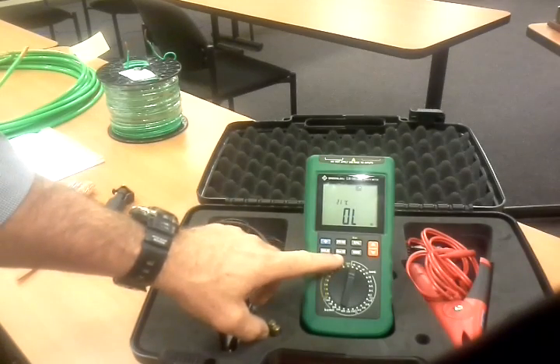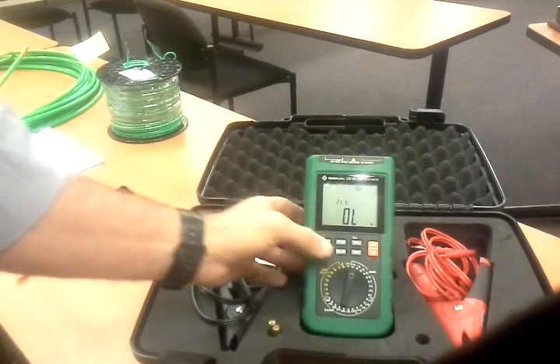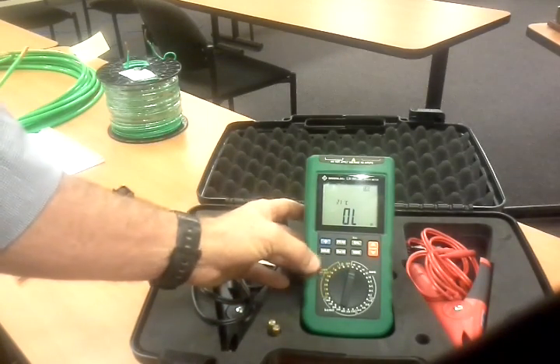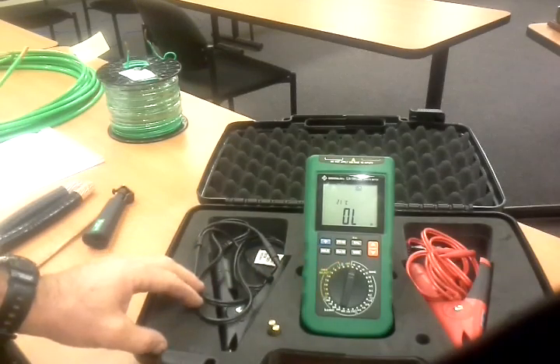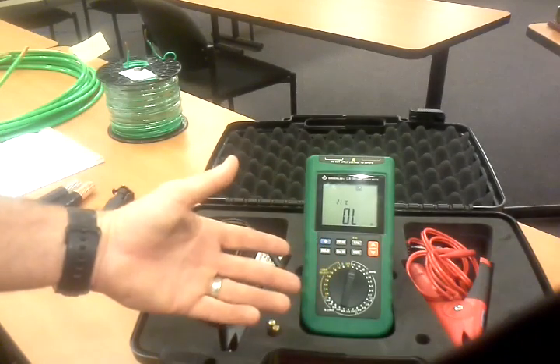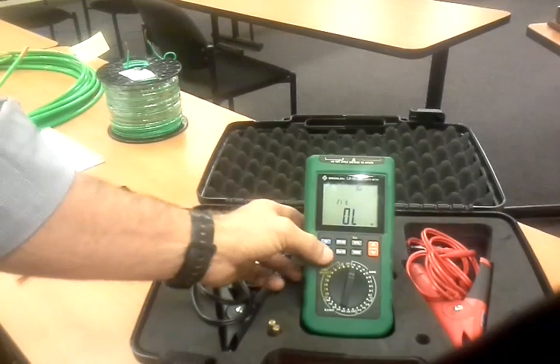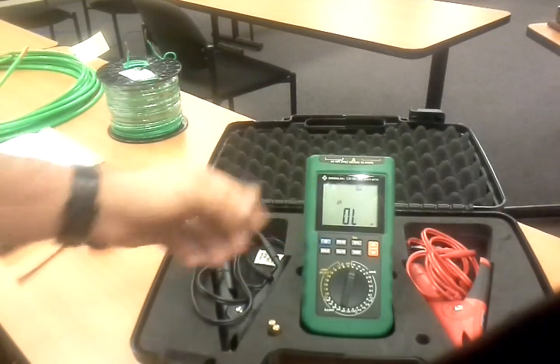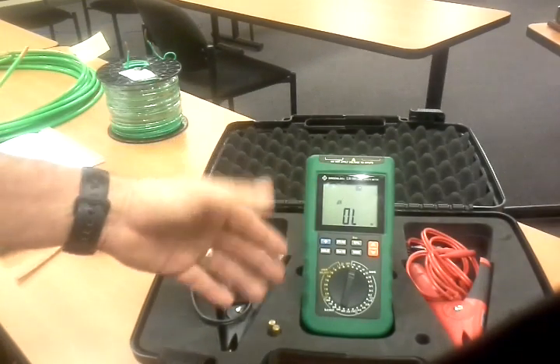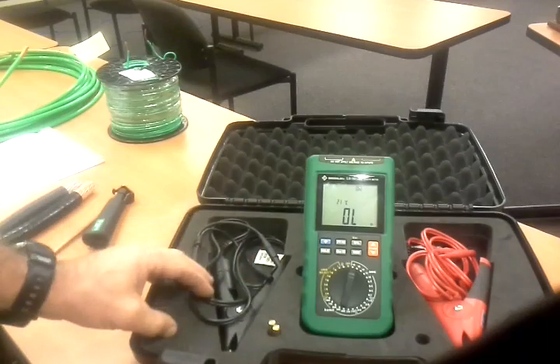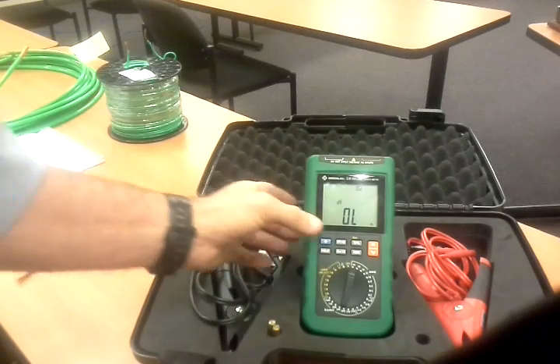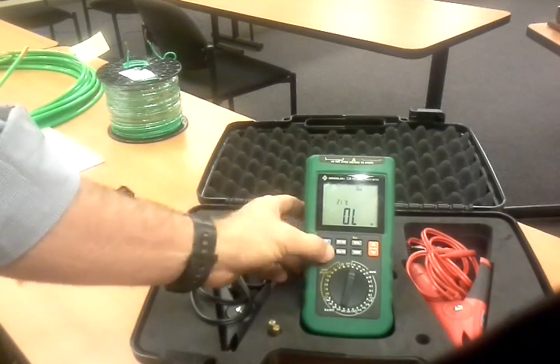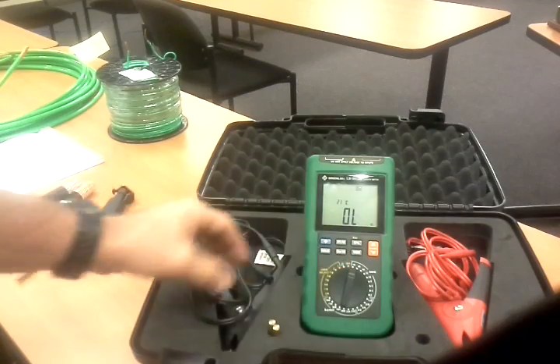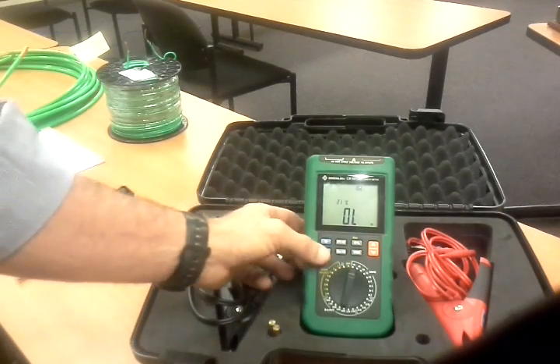It'll also read copper and aluminum cable. So it's set to copper now. One press, go to aluminum, back to copper. The hold button: once you make a reading, you want to hold that measurement, you can press the hold button. You'll see the DH for data hold. It'll keep that reading on there. To turn it off, press again. You can also turn the hold off by pressing the feet and inches, or by pressing copper aluminum.